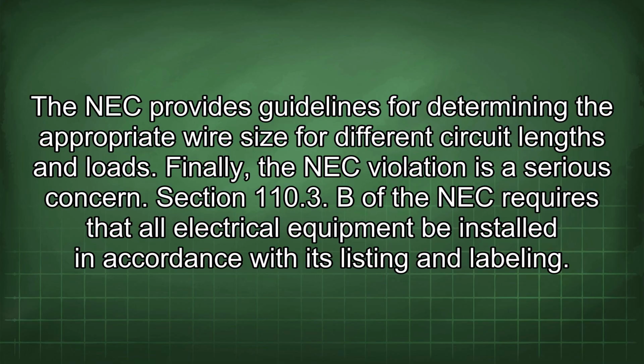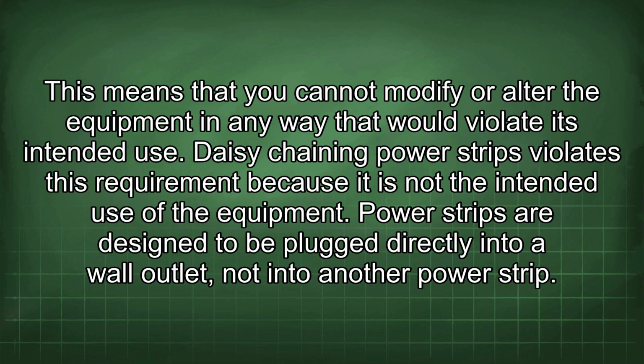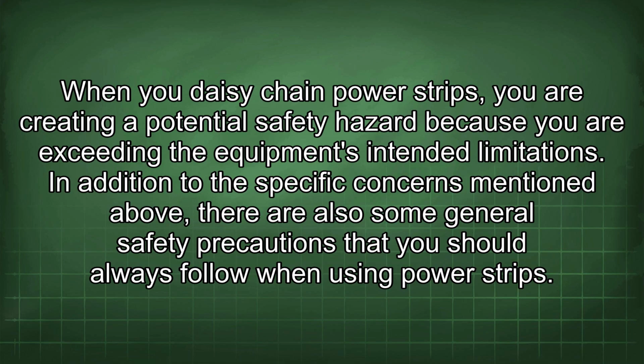Section 110.3 B of the NEC requires that all electrical equipment be installed in accordance with its listing and labeling. This means that you cannot modify or alter the equipment in any way that would violate its intended use. Daisy-chaining power strips violates this requirement because it is not the intended use of the equipment. Power strips are designed to be plugged directly into a wall outlet, not into another power strip. When you daisy-chain power strips, you are creating a potential safety hazard because you are exceeding the equipment's intended limitations.